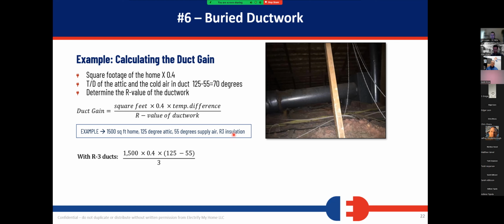So if we have R3 ductwork, we take that 1,500 square foot house and multiply it by 0.4, which gives us the internal surface area of the ductwork. Then we multiply that by the temperature difference between the attic space and the air going through the ductwork, and then we divide that by the insulation value. So 42,000 divided by 3. That means 14,000 BTUs of capacity are going to need to be replaced into the system just to keep those ducts neutral when the attic is 125 degrees.